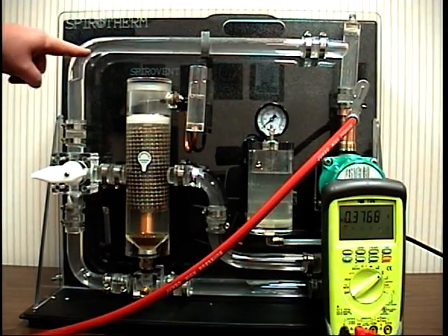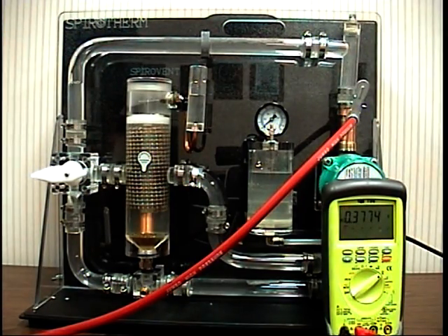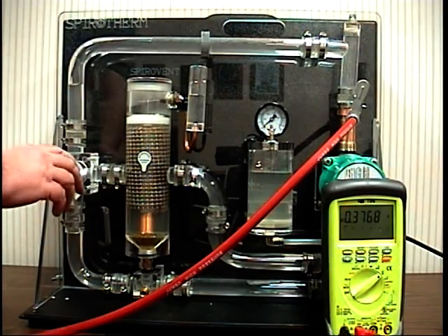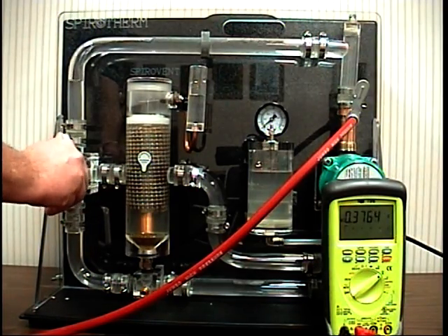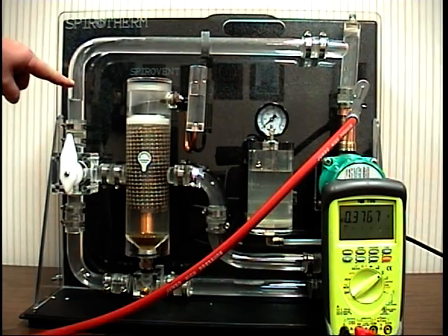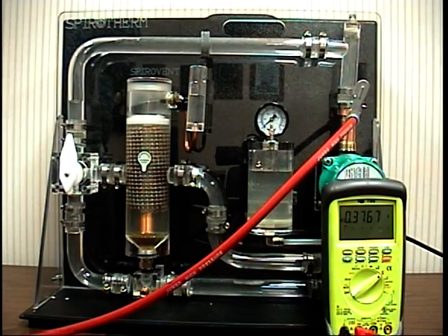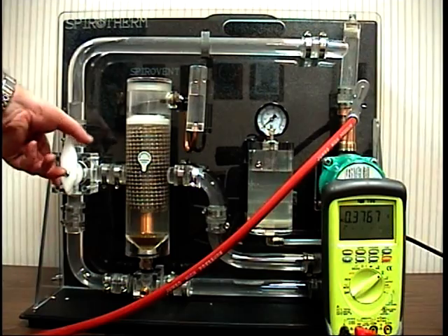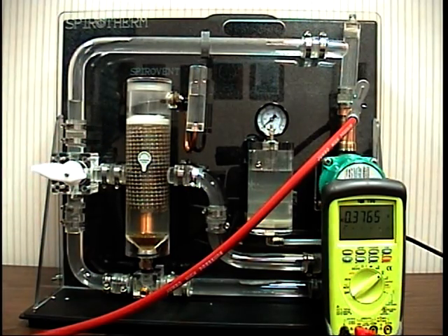Basically, if you look here, this is air actually trapped within the system. Now we're going to open this valve up and force some of the air through the system, through the air separator. Right now we've got such a big air blockage in here that we're not getting air. Before I start forcing that through, I'll show you one other thing that affects the system.